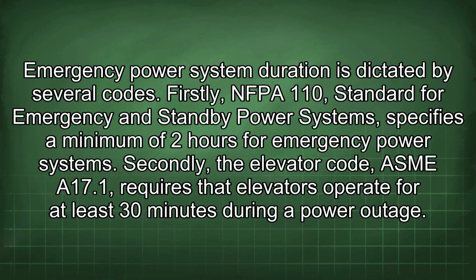Emergency power system duration is dictated by several codes. Firstly, NFPA 110, Standard for Emergency and Standby Power Systems, specifies a minimum of 2 hours for emergency power systems. Secondly, the Elevator Code, ASME A17.1, requires that elevators operate for at least 30 minutes during a power outage.